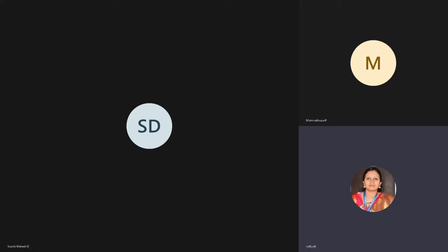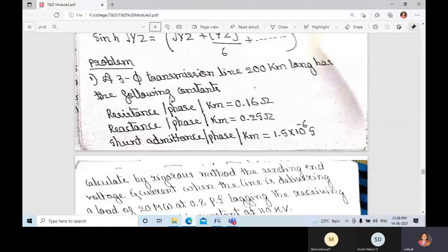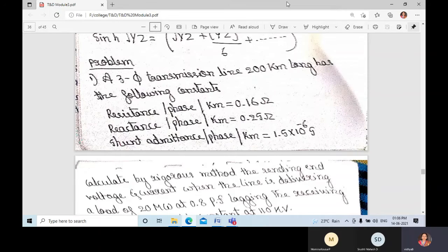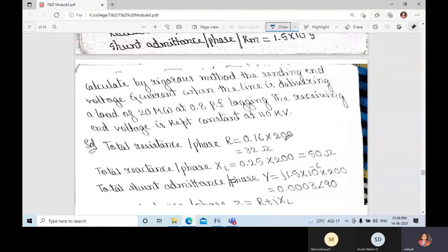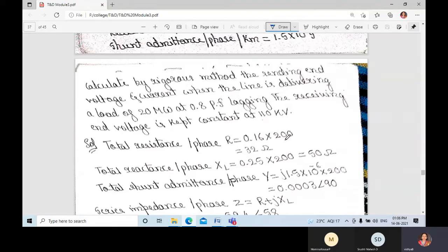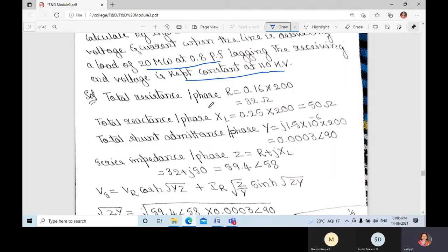In the last class we discussed about long transmission lines. Today we shall discuss problems. The problem is: a transmission line 200 kilometers long has the following constants — resistance per phase per kilometer, reactance per phase per kilometer, and shunt admittance per phase per kilometer. We need to calculate the sending end voltage and current while the line is delivering a load of 20 megawatt at 0.8 power factor lagging, with the receiving end voltage kept constant at 110 kV.